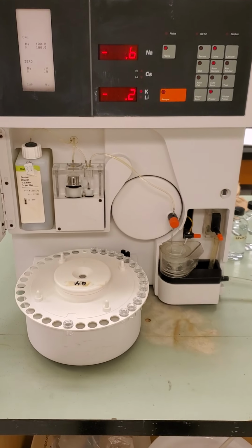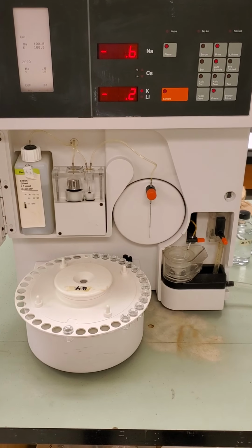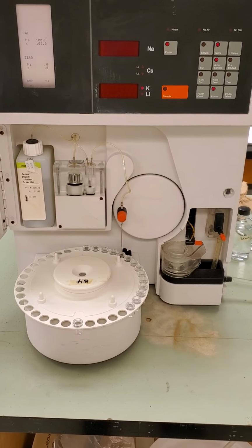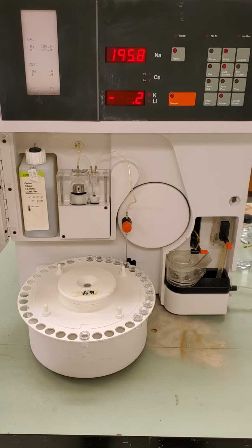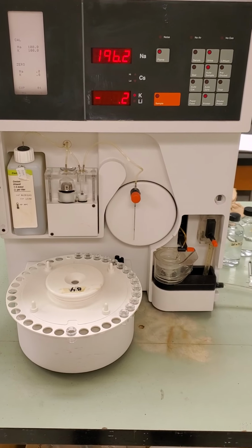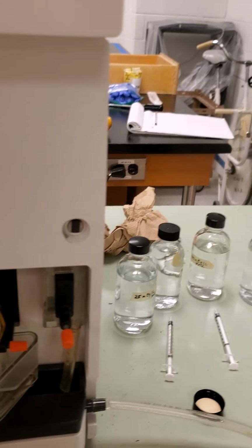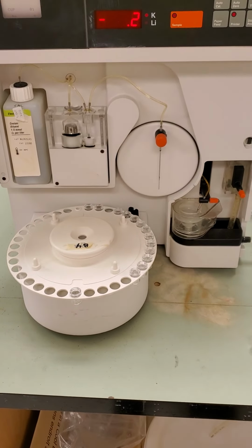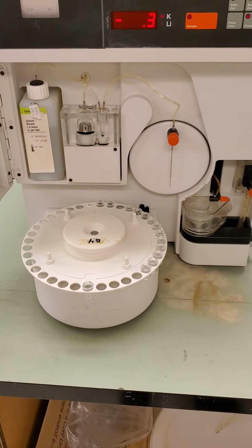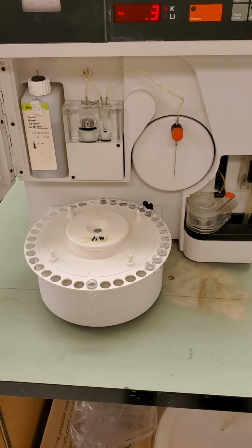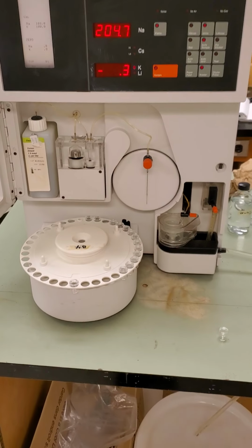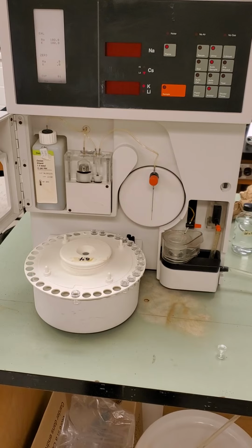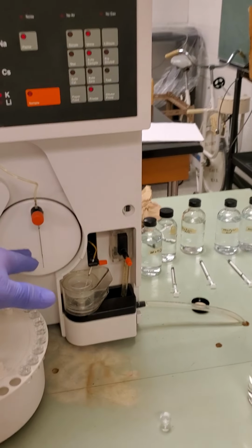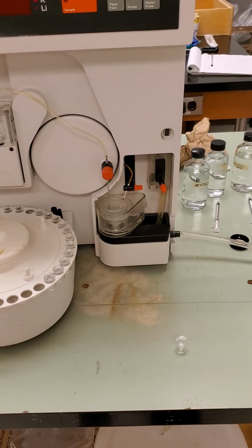So let's see how once it starts sampling it. Now the machine doesn't like readings that are over, I guess this is 200. Somehow it didn't get that first sample. That's why 250 didn't show up. So this is the 200. I don't think I had the level of the sample high enough and it missed it. So that's why it showed next to nothing there, because it got no sample. This one, about 200. It waits for it to stabilize, and then it'll print it out. And it's already got the other sample in the needle here, and it's going to put it into the mixing chamber. And so this one is, I believe, 140.